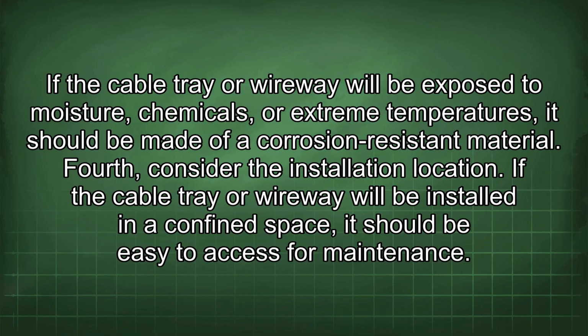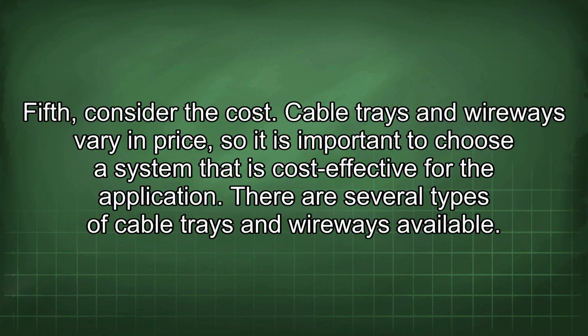If the cable tray or wireway will be exposed to moisture, chemicals, or extreme temperatures, it should be made of a corrosion-resistant material. Fourth, consider the installation location. If the cable tray or wireway will be installed in a confined space, it should be easy to access for maintenance. Fifth, consider the cost. Cable trays and wireways vary in price, so it is important to choose a system that is cost-effective for the application.